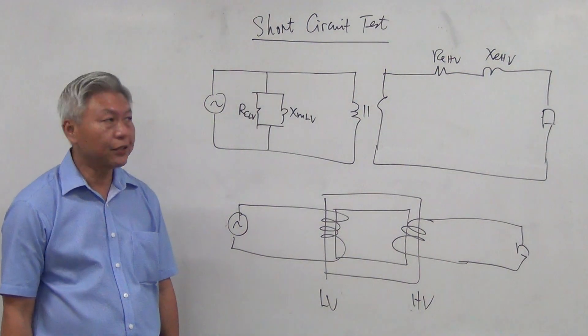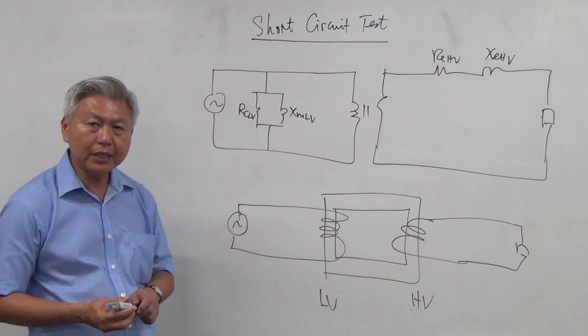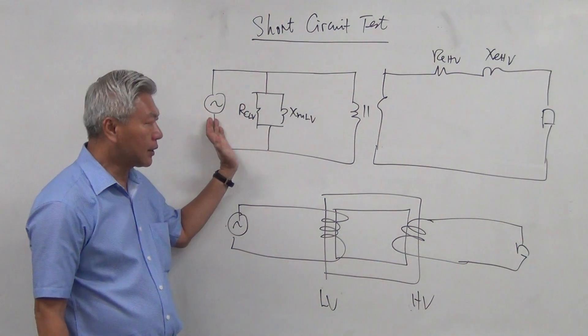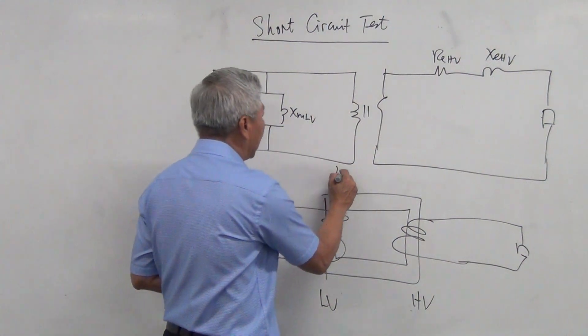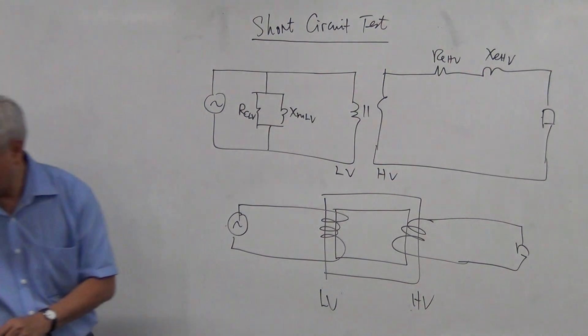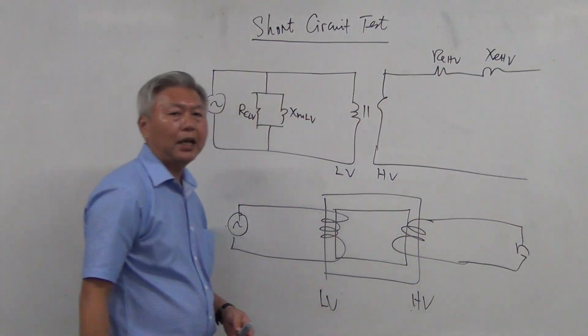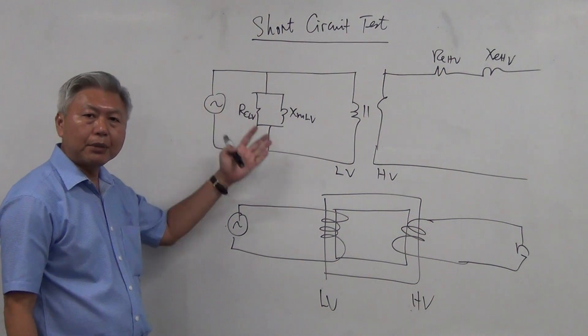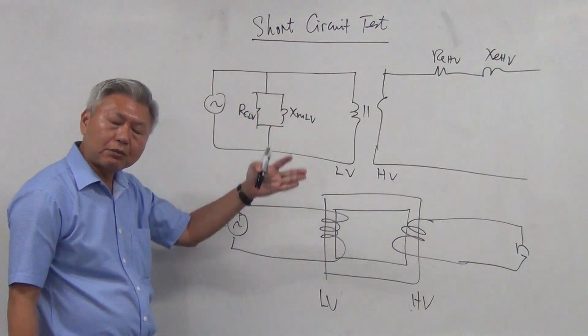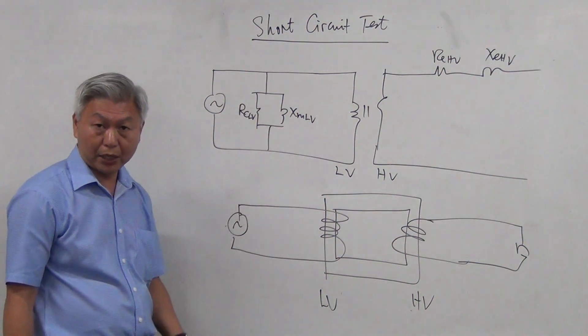We have just learned the open circuit test. The open circuit test was an experiment where we connect the power supply to the low voltage side and leave the high voltage side open circuit. We used voltmeters, ammeters, and wattmeters to measure the readings, and then went through a series of steps to get the values of RC and XM.